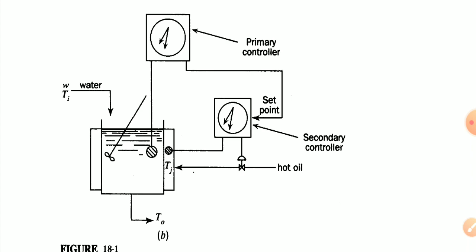The effect has to work itself through several resistances to reach the measuring element. To prevent the sluggish response of the kettle temperature to disturbance in oil supply temperature, the control system shown in figure 18 is proposed, which includes two controllers and two measuring elements. The output of the primary controller is used to adjust the set point of the secondary controller, which is used to control the jacket temperature.